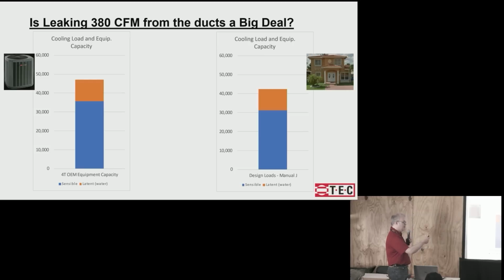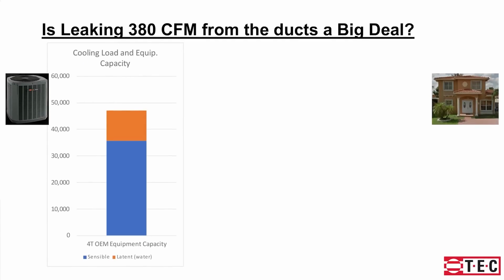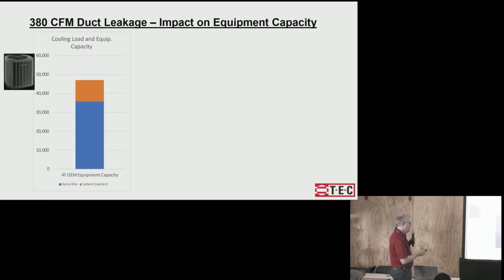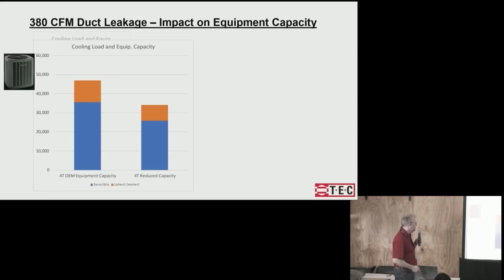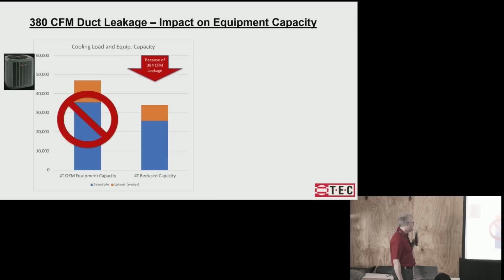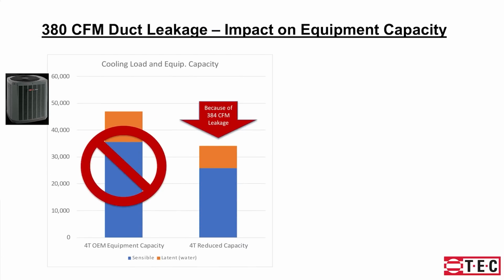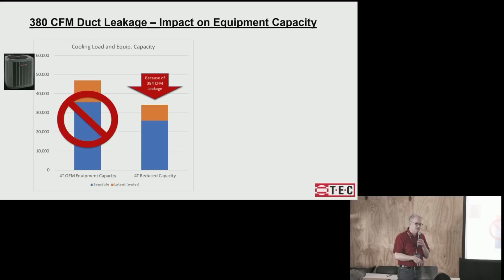We're going to look at each side separately and what this leakage to outside does to the capacity. Okay, so we started here with this 4-ton system that has latent and sensible capacity, and then we took about a quarter of the air and we blew it outside. Okay, so what do you have? You have reduced capacity. You blow a quarter of the air outside, you've only got about 3/4 of the capacity that you thought you had. Very simple, right? If the air didn't come back into the house, it didn't cool anything down. It probably cooled the attic down a little bit, but good luck doing that.